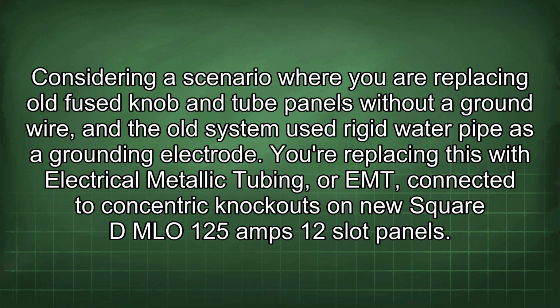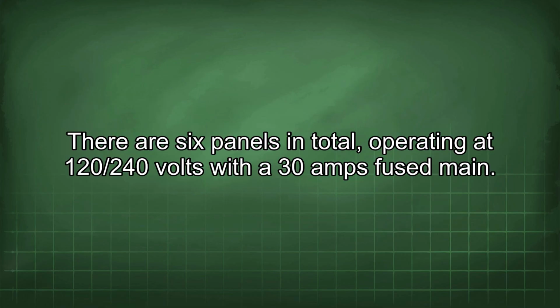Considering a scenario where you are replacing old fused knob and tube panels without a ground wire, and the old system used rigid water pipe as a grounding electrode. You're replacing this with electrical metallic tubing, or EMT, connected to concentric knockouts on new square D MLO 125 amp 12-slot panels. There are 6 panels in total, operating at 120/240 volts with a 30 amp fuse main.